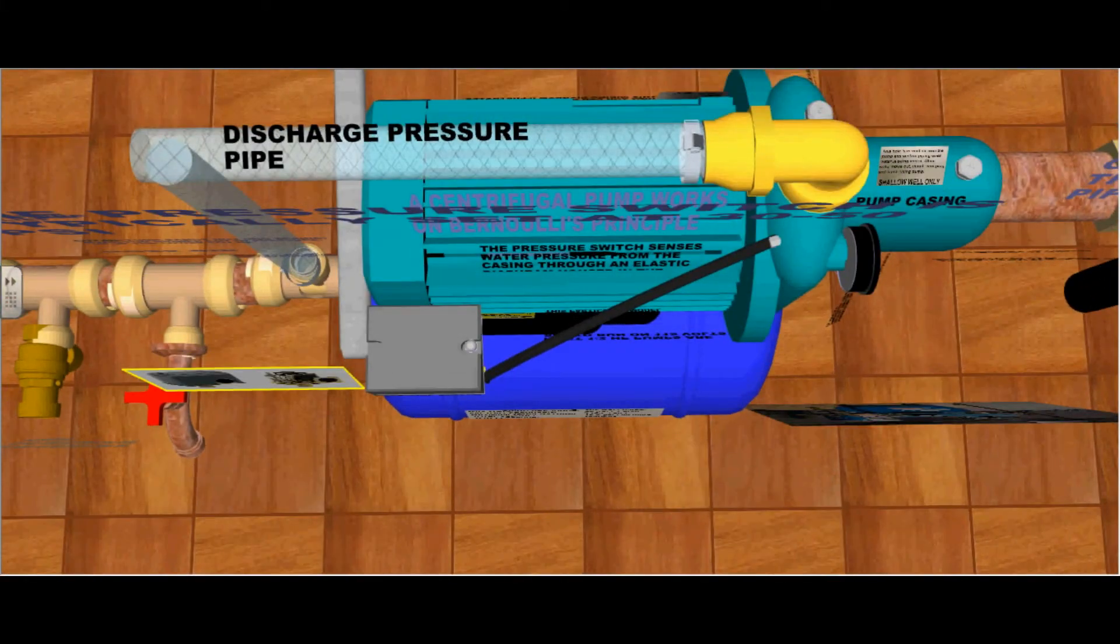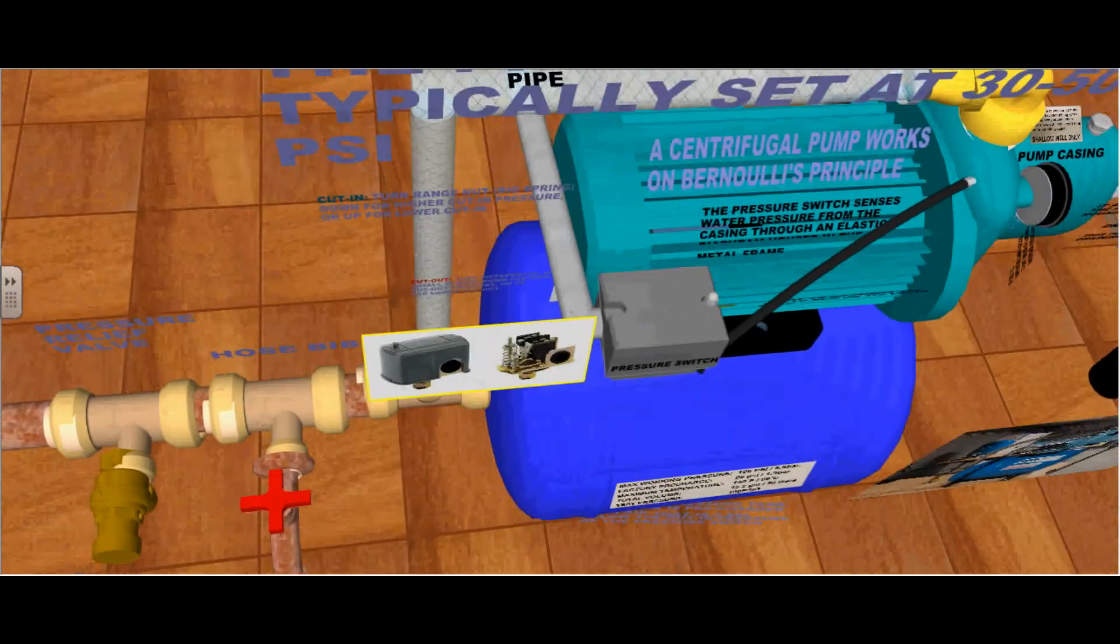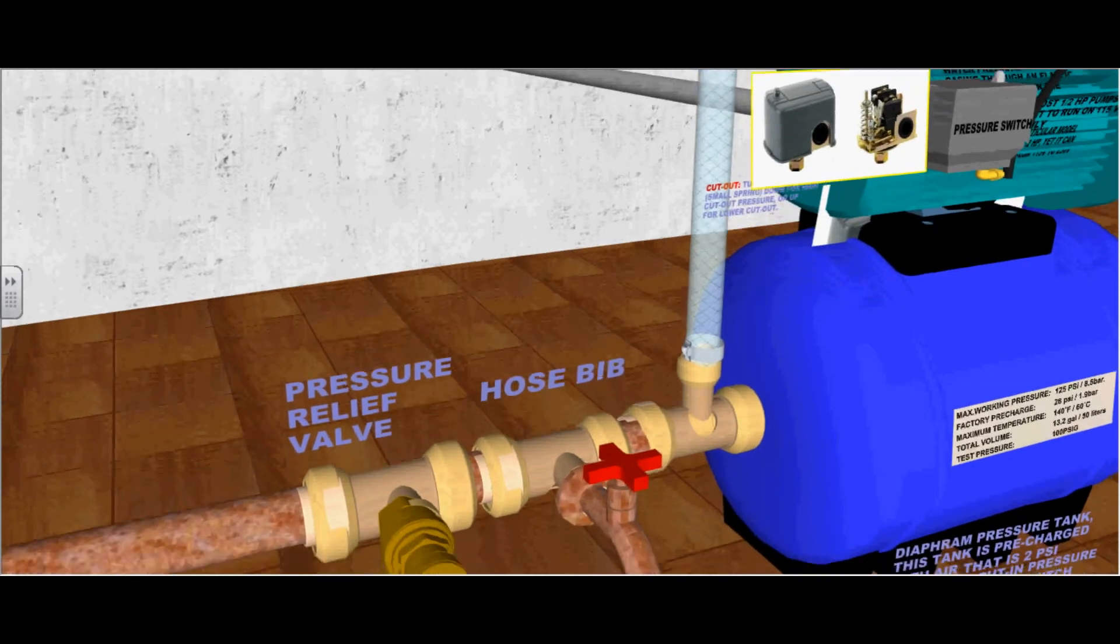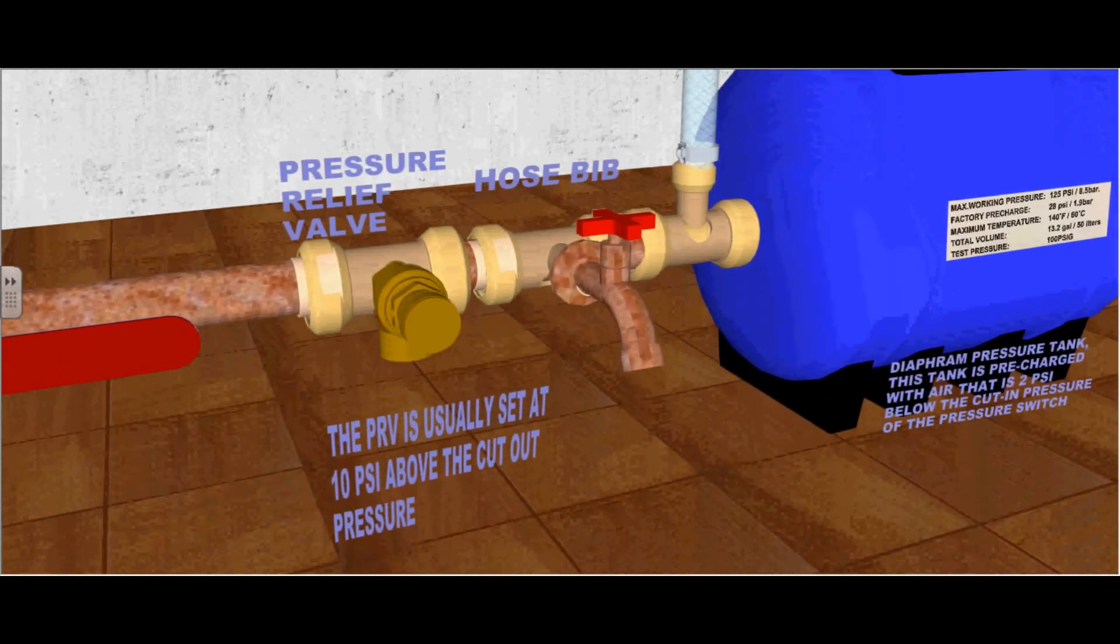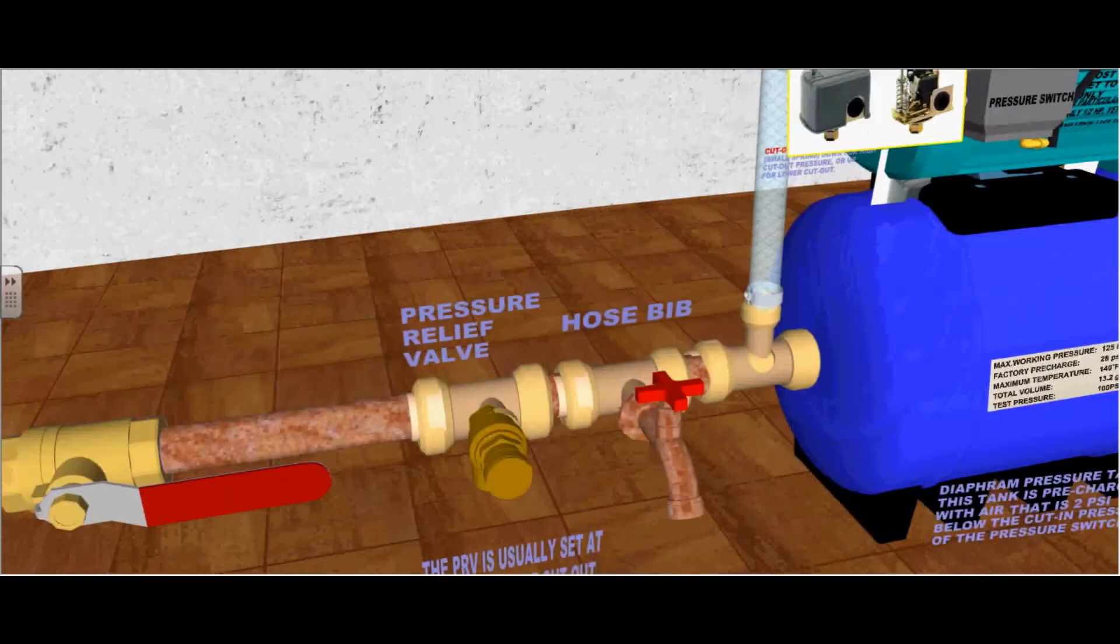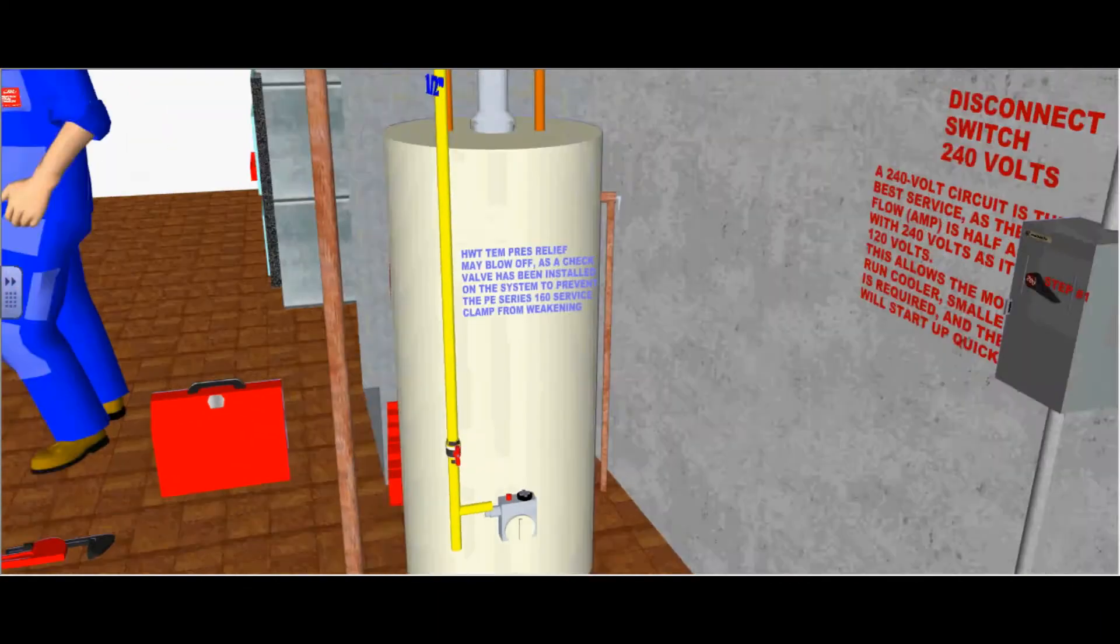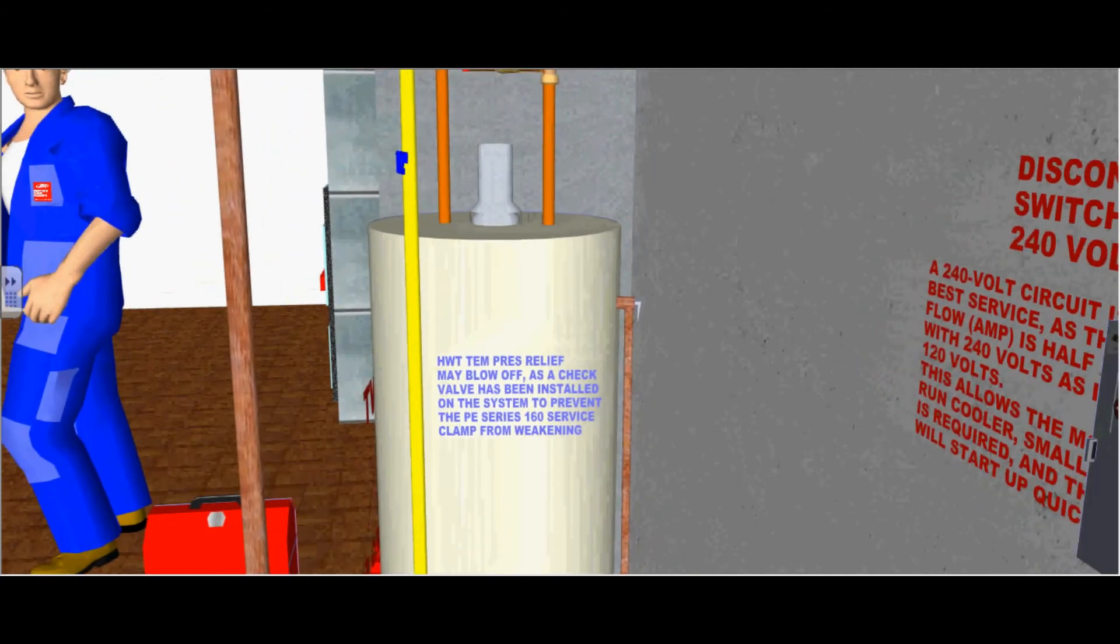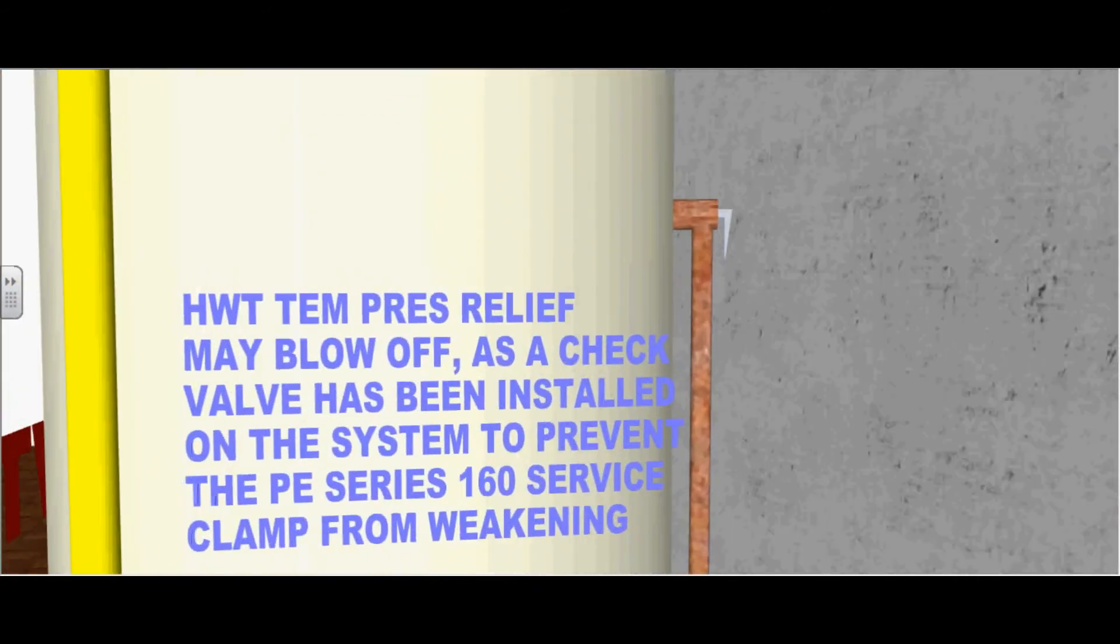This is the discharge pressure pipe coming from the volute casing. Here is a hose used to test the water and purge the system. This pressure relief valve is usually set at 10 psi above the cut-out pressure. In this particular case, the hot water tank temperature pressure relief valve may blow off as a check valve has been installed in the system to prevent the polyethylene service clamp from weakening.